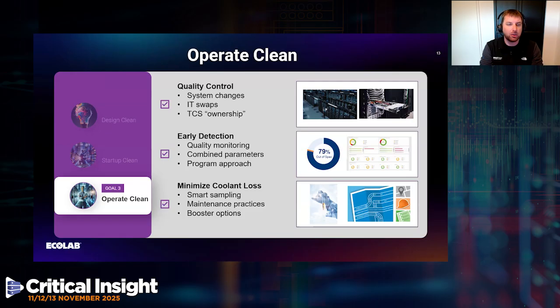And this highlights also the importance that just taking a sample once in a while might not cover it for your facility. These loops are under a lot of stress. They do see a lot of cycles. And even with the increase of AI and machine learning, what we often see is that these systems are operating in a peak load with some idle time, with a peak load again. And then it gets especially important to have maybe some online monitoring equipment in there that tracks the condition of the coolant, that tracks if the coolant is degrading, and also manages to track some early warning signs, for example, bio or corrosion.